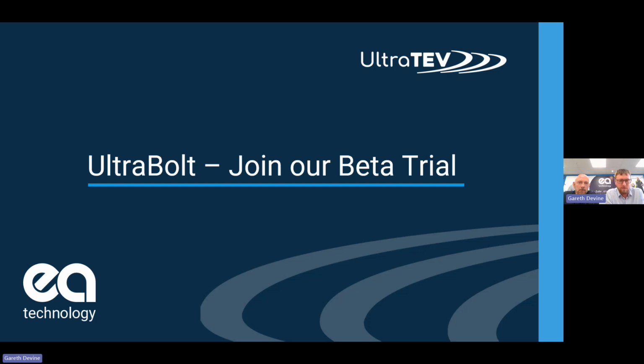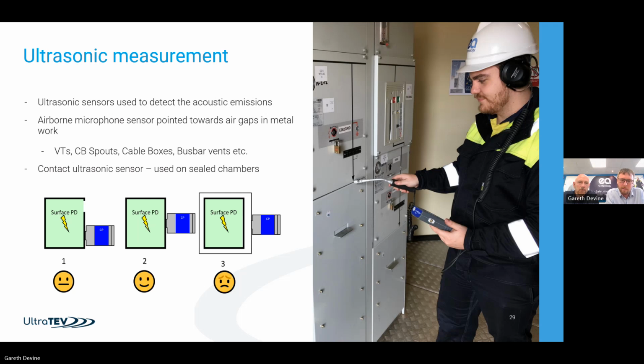The UltraBolt is our latest accessory. This basically takes ultrasonics, which we currently measure on metal clad switchgear using airborne microphones, so looking for acoustic emissions. A photograph here of Tom from our Australian office. He's scanning around the gaps in the metalwork, where the metalwork joins together, and that works. It's quite effective. We can see from that how the small air gap will allow the energy from the PD to escape, and you can detect it quite efficiently, but it is very localized.